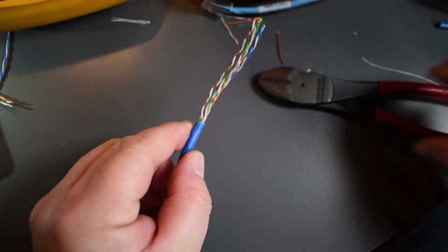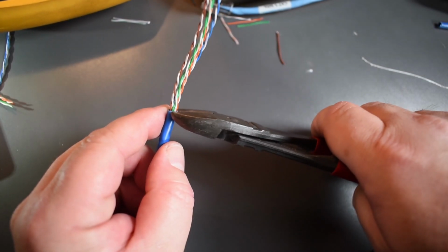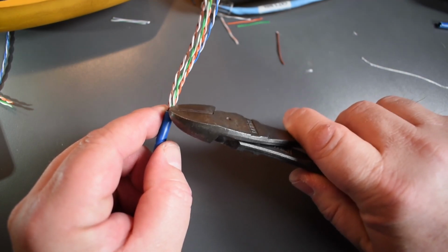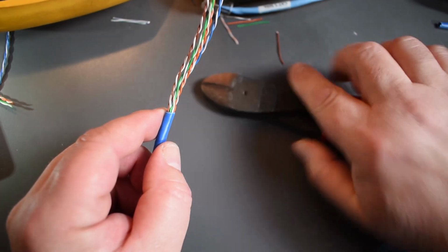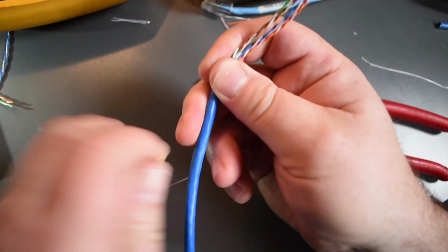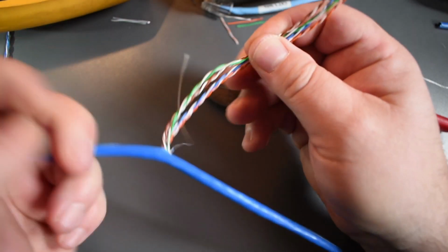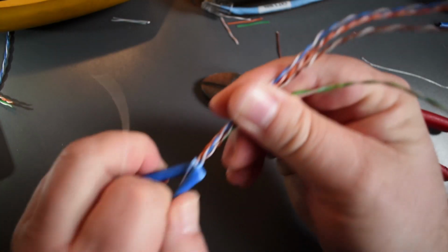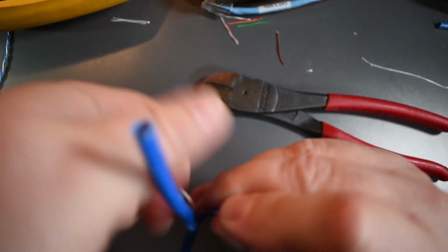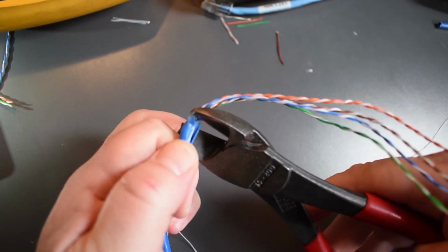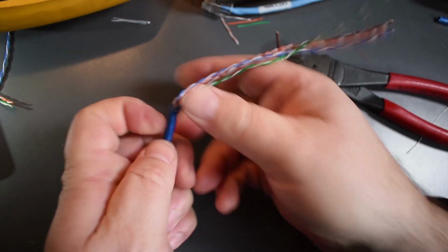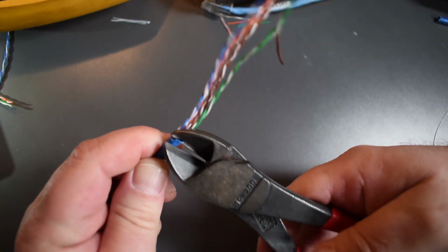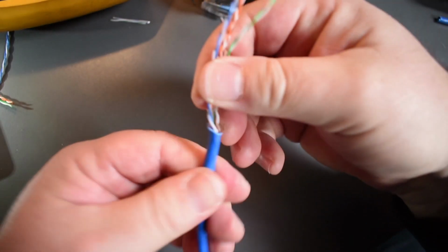Remember, once you nick this part with the side cutters, that part right here is always going to get damaged. So don't use those conductors past this point. Okay, so that's why we use the ripcord. Just going to pull a little bit more, peel it, then cut the fluff. We always cut the fluff, and we have to make sure that this part is as rounded as possible. So I'm just going to do some grooming here.